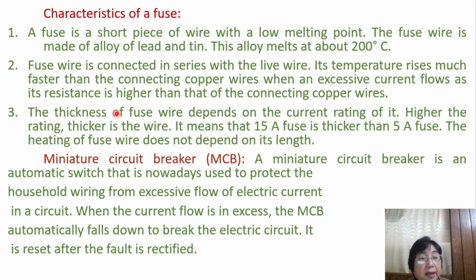Point number 3: the thickness of the fuse wire depends on its current rating. Higher the rating, thicker is the wire, meaning a 15 ampere fuse is thicker than a 5 ampere fuse. The heating of the fuse wire does not depend on its length; it depends on the melting point, high resistance, and also the thickness. So we use a thicker wire for higher current carrying capacity, and a thinner fuse wire for lower current carrying capacity. Thicker the wire, higher is the rating.